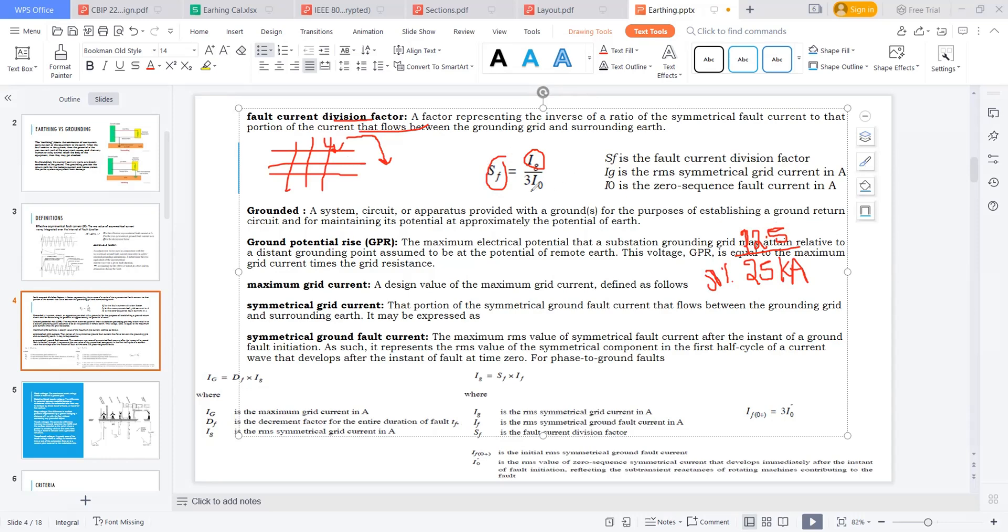Here, 3I₀ is the zero sequence fault current, which is the maximum fault current when a three-phase to ground fault occurs. All three phases are coming into the neutral. 3I₀ in the worst case: for 220kV, we consider 40kA; for 33kV, 25kA; for 132kV, 31.5kA; and for 400kV, 50kA or 63kA depending on the project.